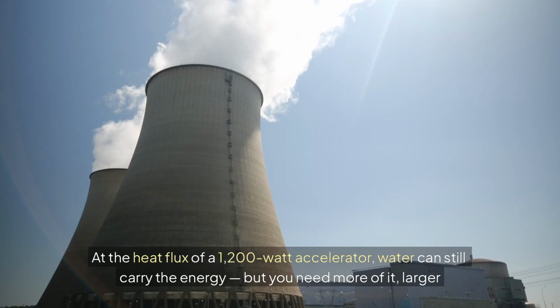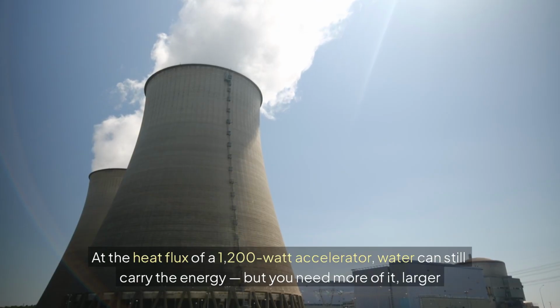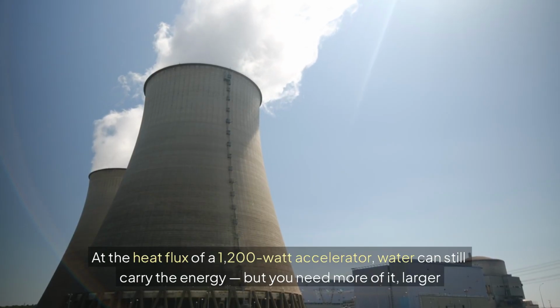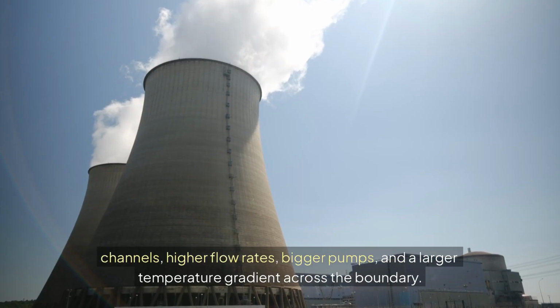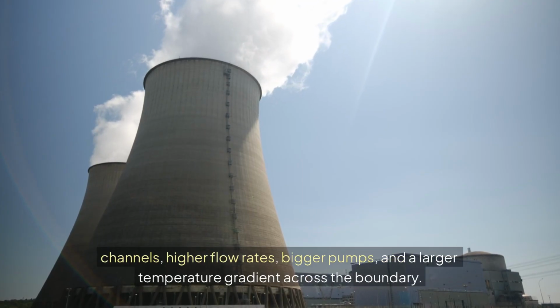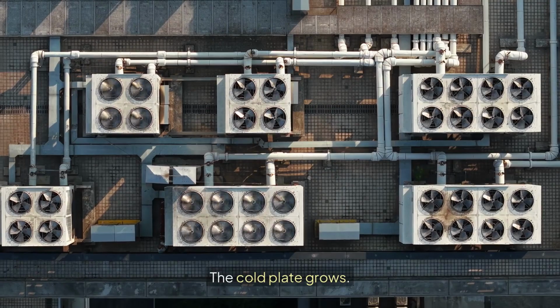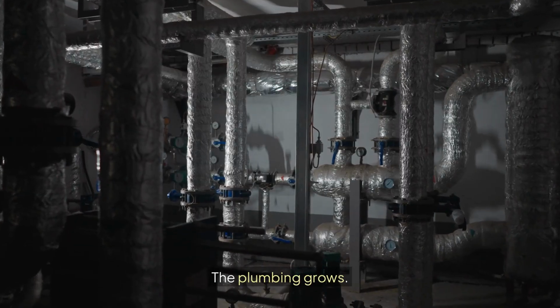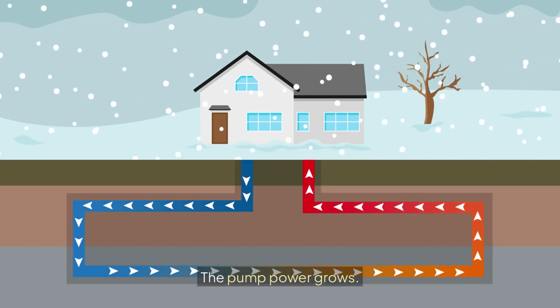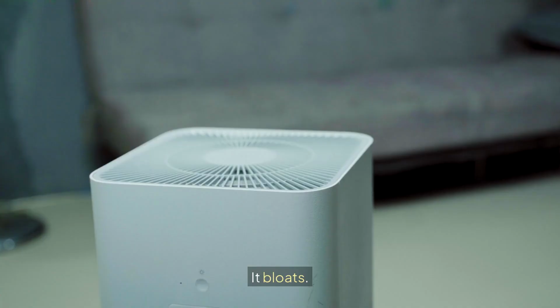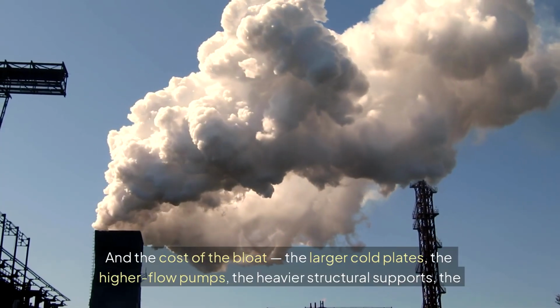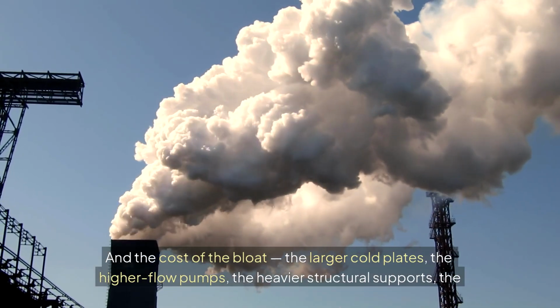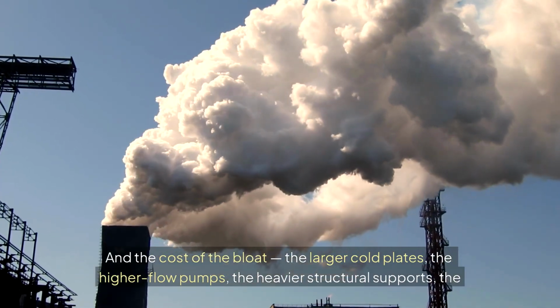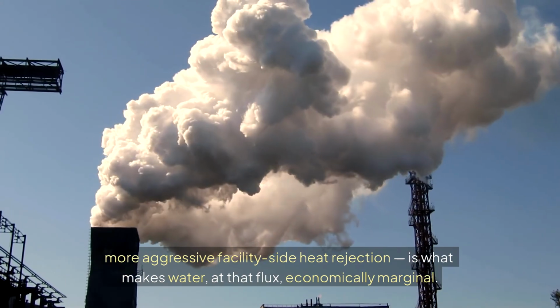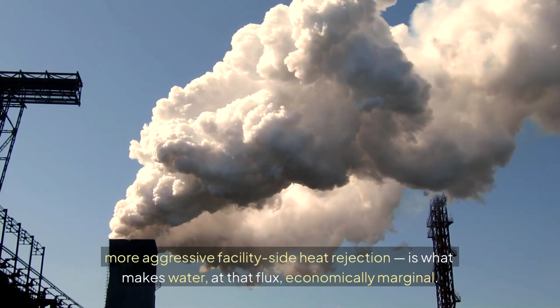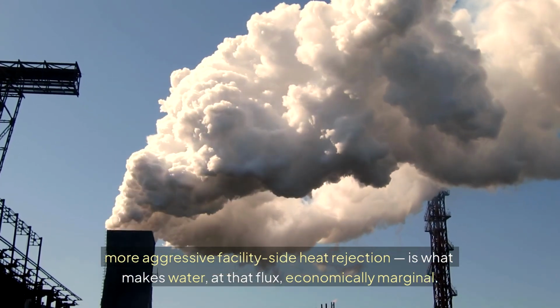At the heat flux of a 1,200-watt accelerator, water can still carry the energy, but you need more of it. Larger channels, higher flow rates, bigger pumps, and a larger temperature gradient across the boundary. The cold plate grows. The plumbing grows. The pump power grows. The system does not break. It bloats. And the cost of the bloat, the larger cold plates, the higher flow pumps, the heavier structural supports, the more aggressive facility-side heat rejection, is what makes water at that flux economically marginal.